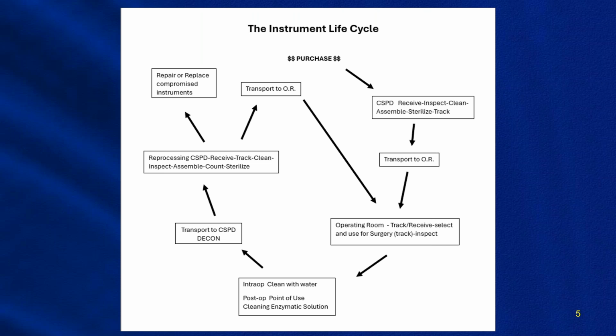Intraoperatively, instruments need to be wiped down with clean water by the surgical tech or the RN scrub. And immediately after the procedure, we'll talk about the postoperative point of use cleaning and treatment with enzymatic solutions. From that point, the treated and soiled instruments will be transported to the central sterile processing department for instrument reprocessing. The trays will be cleaned, inspected, assembled, counted, and re-sterilized. And if the trays meet all parameters for inspection and sterilization, they will be tracked and transported back to the OR for reuse. If any instruments fail inspection, they will be sent out for repair or replacement.